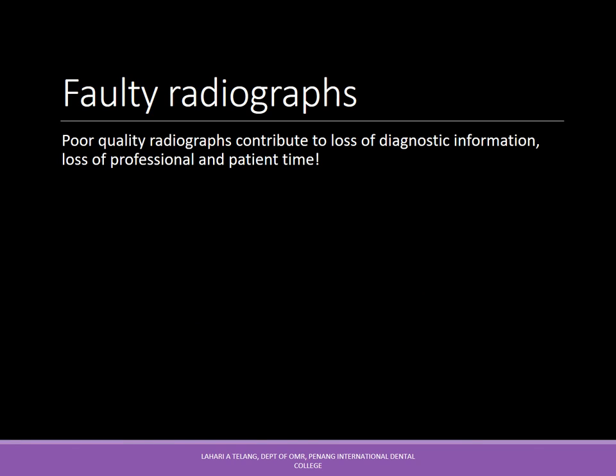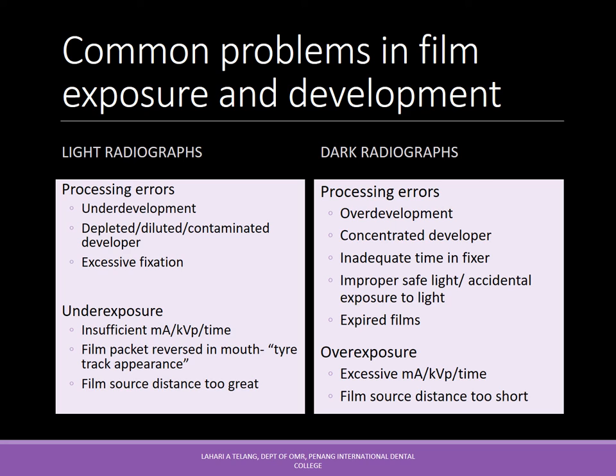Poor quality radiographs contribute to loss of diagnostic information and loss of professional and patient time. Common problems include light radiographs — caused by processing errors such as underdevelopment, depleted or contaminated developer, excessive fixation; underexposure from insufficient current, voltage, or time; reversed film packet in the mouth causing a tire-track appearance; or film-source distance being too great. Dark radiographs can result from processing errors like overdevelopment, concentrated developer, inadequate fixer time, improper safe light, accidental light exposure, or expired films. Overexposure causing dark radiographs results from excessive current, voltage, time, or film-source distance being too short.